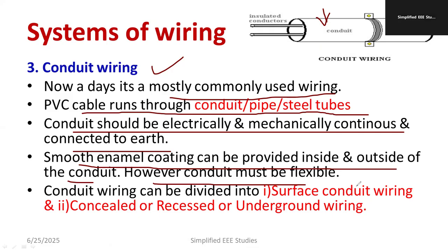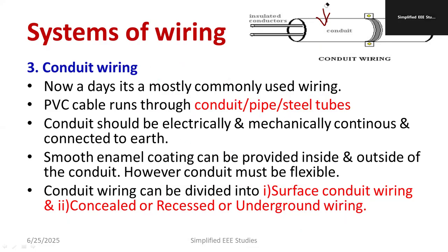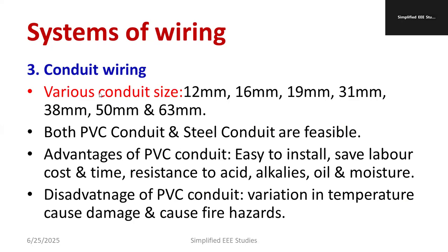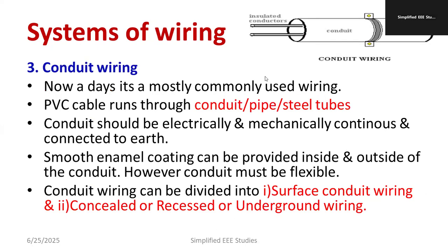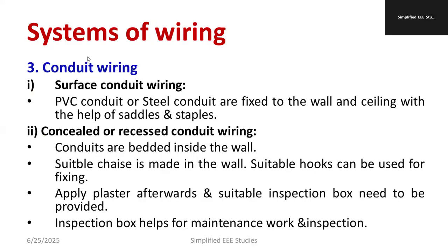Conduit wiring is broadly classified into two types: surface conduit wiring and concealed or recessed wiring. Different sizes of conduits are available — 12, 16, 19, 31, 38, 50, and 63 millimeters — chosen depending on the installation. Both PVC conduits and steel conduits are available. Advantages of PVC conduits include easy installation, saving labor cost and time, and resistance to acid, alkalis, oils, and moisture. A drawback is temperature variation, which can cause melting or damage.